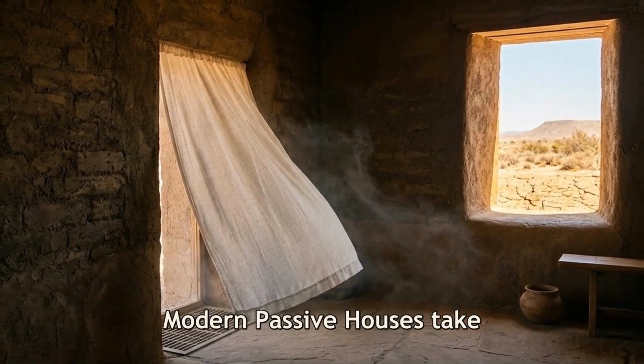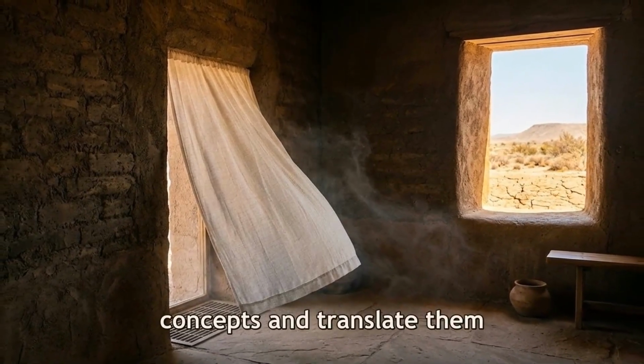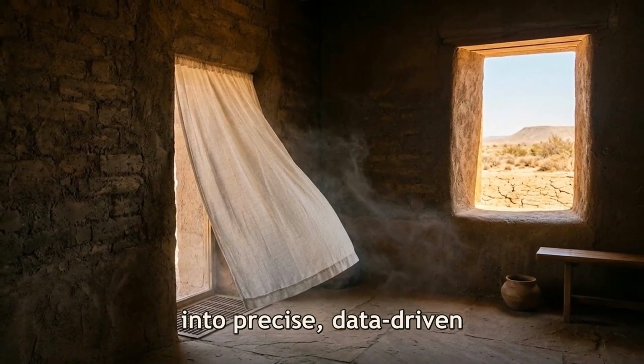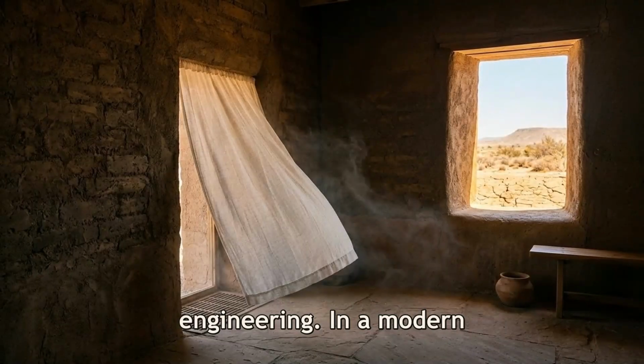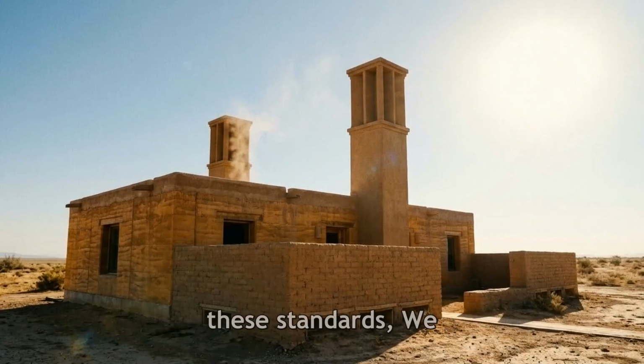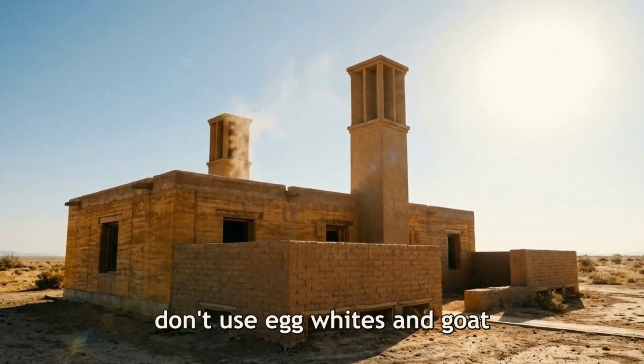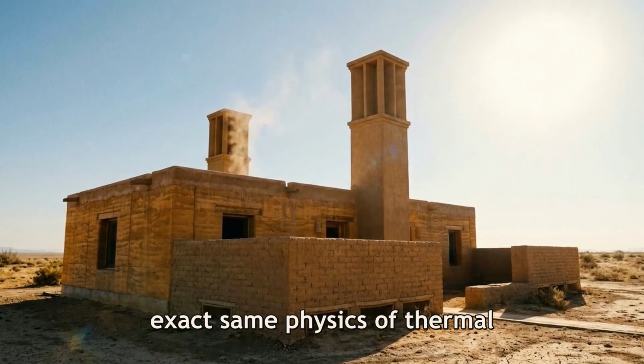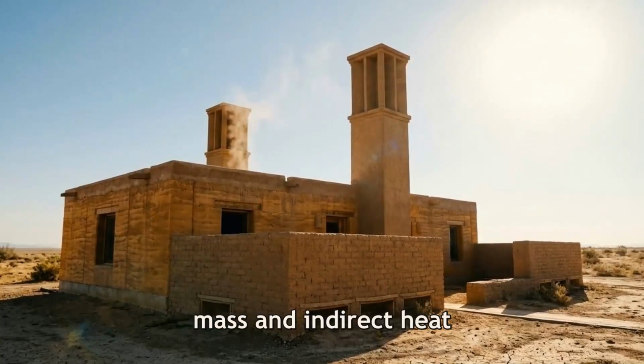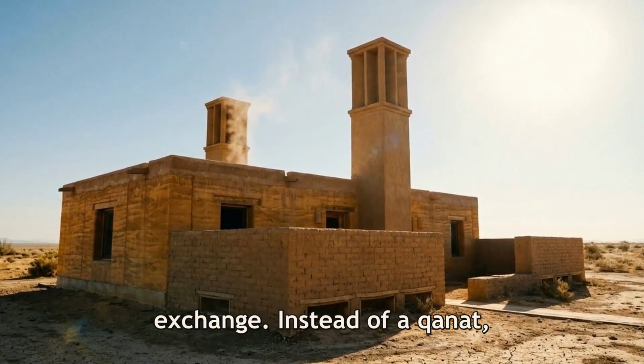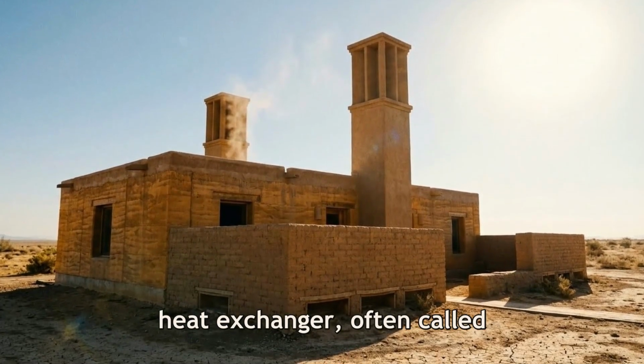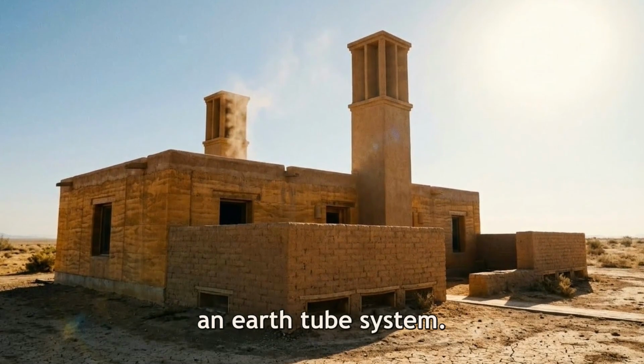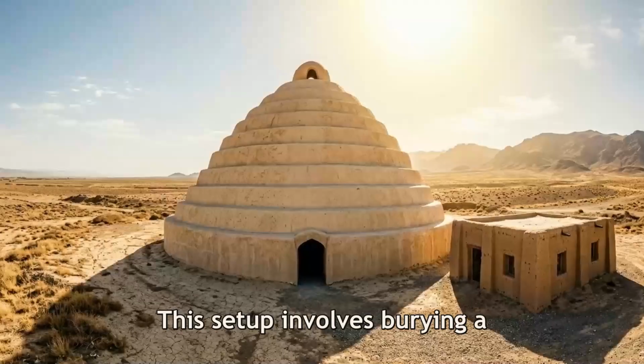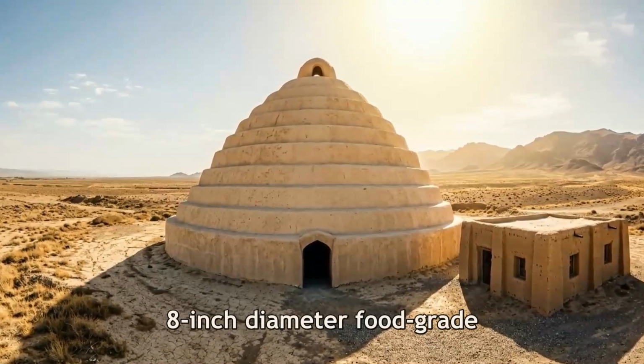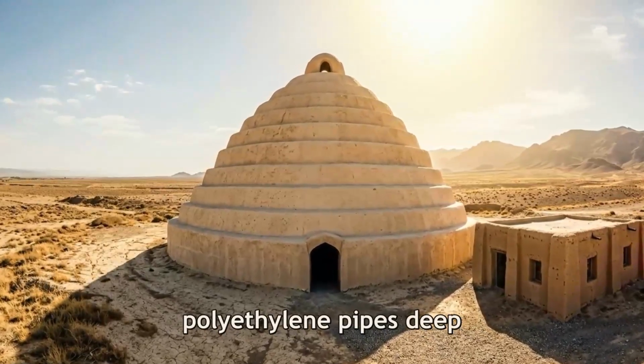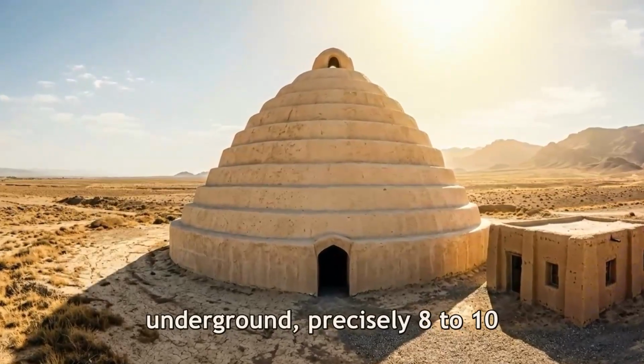Modern passive houses take these exact historical concepts and translate them into precise, data-driven engineering. In a modern off-grid passive home built to these standards, we don't use egg whites and goat hair, but we use the exact same physics of thermal mass and indirect heat exchange. Instead of a qanat, we install an earth-air heat exchanger, often called an earth tube system. This setup involves burying a network of 6-inch to 8-inch diameter, food-grade polyethylene pipes deep underground, precisely 8 to 10 feet below the surface.